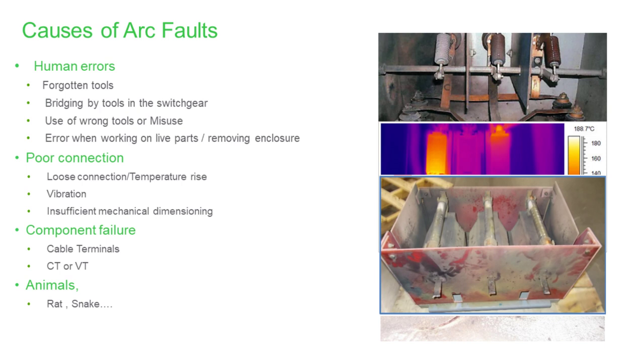What causes the arc? One of the first causes is human error — forgotten tools, bridging by tools in switchgear, using the wrong or misused tools, errors while working with live parts such as moving the enclosure door. In this picture, we can see a wrench left causing a short circuit between phase and ground. Another cause is poor connection, due to loose connections — as seen in the thermal image — vibration, and insufficient mechanical design. Another cause is component failure: cable terminals, CT/VT components can be damaged. And lastly, animals — rats, snakes — anywhere around the system, depending on your geographical location.